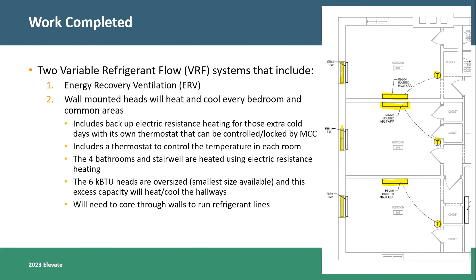The exhaust air ducts and supply air ducts from the dedicated outside air system get to the upper floors through a new shaft cut through closets, stacked on top of each other. There were also a lot of holes cut into walls to route the refrigerant pipes where they needed to go, so a fair amount of destruction in this fairly historic building. That's the way it goes sometimes. Okay, on the next photo.